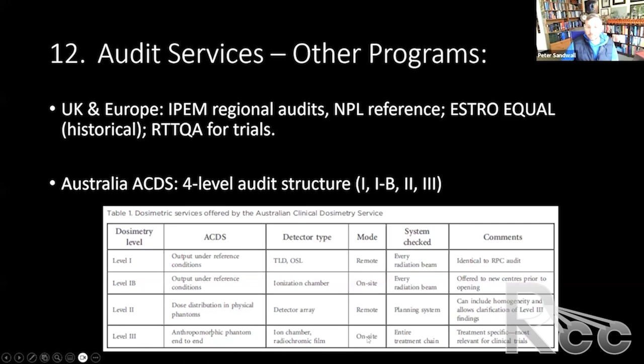It's interesting. I think that a lot of Australian centers use reference beam data. They use the same beam data for accelerators of the same model. So it's very reasonable to expect an IMRT QA in Sydney to get the same result in another city. Then level 3 is an anthropomorphic phantom, such as the head and neck phantoms or pelvis phantoms, and that'll be a complete end-to-end test.